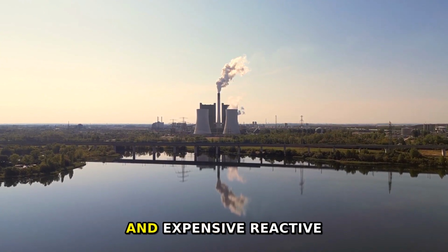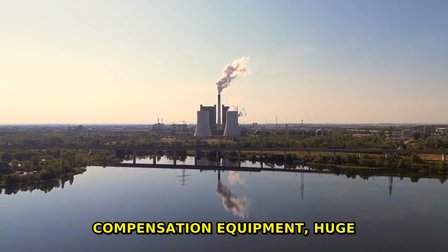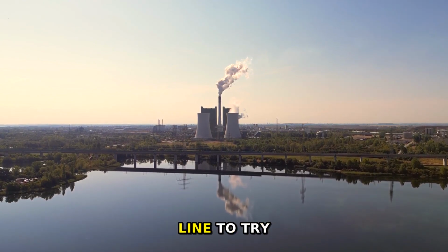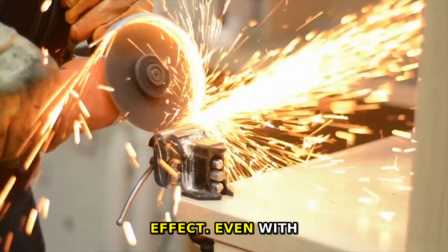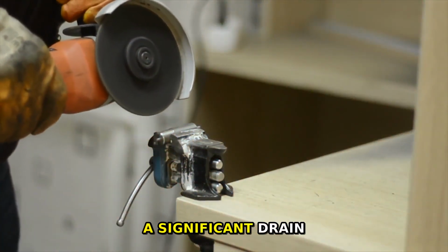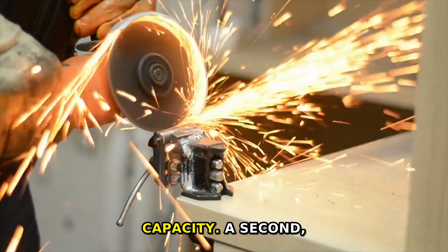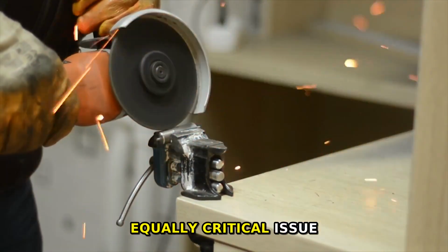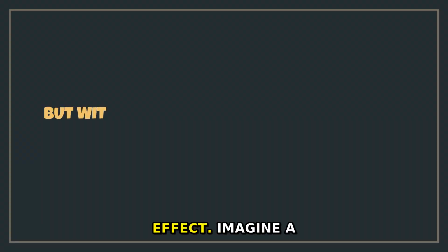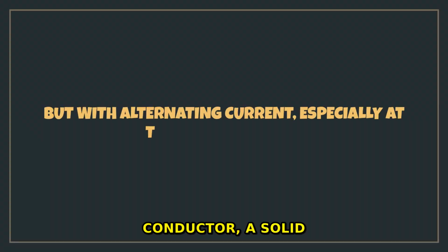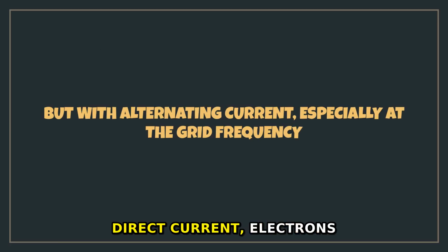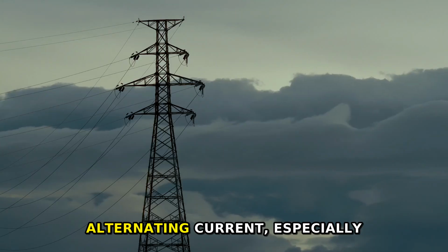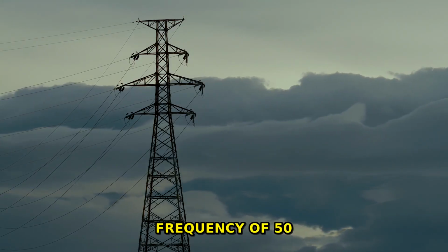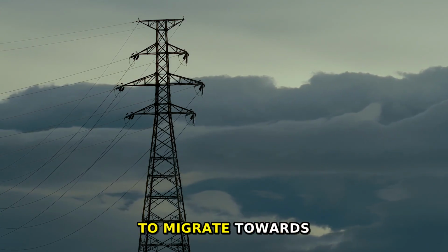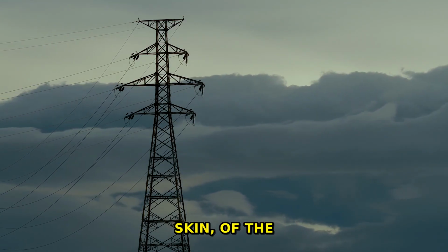Engineers must install bulky and expensive reactive compensation equipment, huge capacitor banks and inductors, along the line to try and minimize this effect. Even with compensation, it remains a significant drain on efficiency and capacity. A second, more subtle, but equally critical issue for AC transmission is the skin effect. Imagine a conductor, a solid copper wire. With direct current, electrons flow evenly through the entire cross-section of the wire. But with alternating current, especially at the grid frequency of 50 or 60 Hz, the electrons tend to migrate towards the surface, or skin, of the conductor.